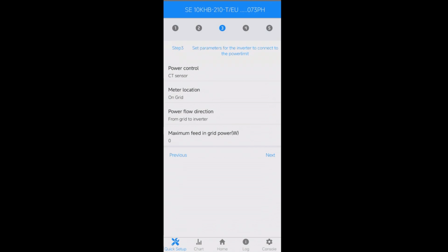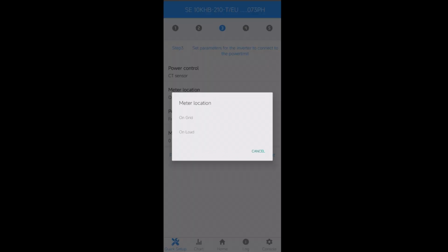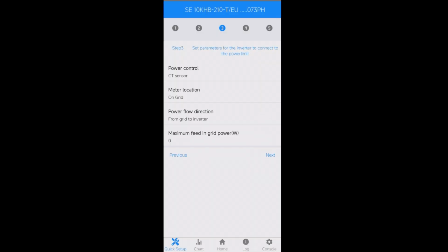And if 10 meters is still too short for any plant, for any installation, maybe you can consider installing a meter, the digital meter. Currently, for the single phase, our inverter is compatible with Chint DDSU666, that one. If you installed it at a wrong location during installation and when you went back to the office you recognize it is wrong, you can make the changes on the app. And then we can change the CT direction. Yes, you can change the direction.